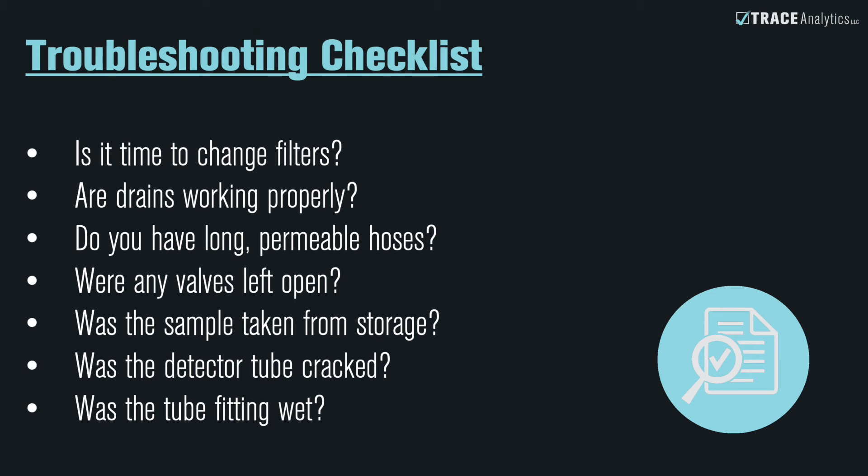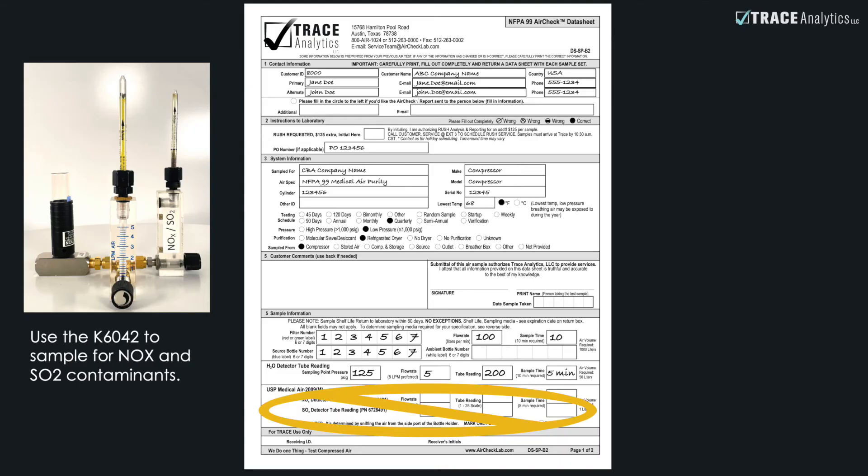If the water vapor sample does not pass, you can take corrective action immediately and then retake the sample. Disregard the NOx and SO2 tube reading section if these were not used. To sample for USP medical air, proceed with the K6042 AirCheck kit.